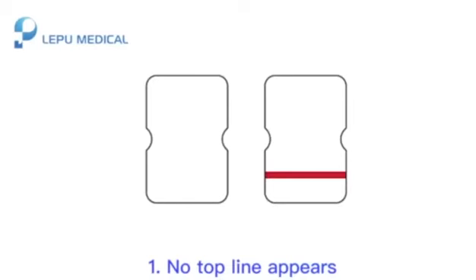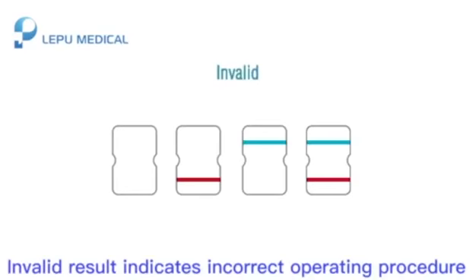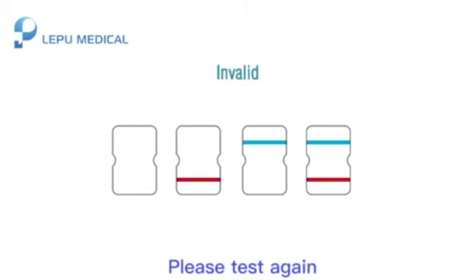The test result is invalid if: 1. No top line appears, or 2. The top line remains blue. An invalid test result indicates an incorrect operating procedure or that the test card has deteriorated. Please test again.